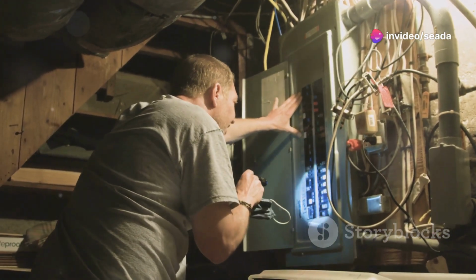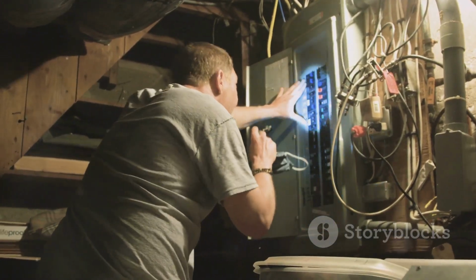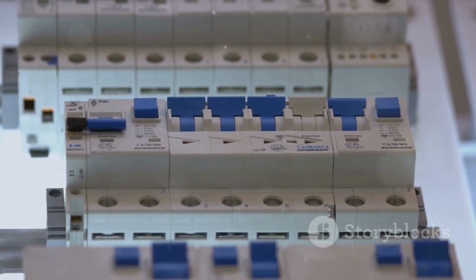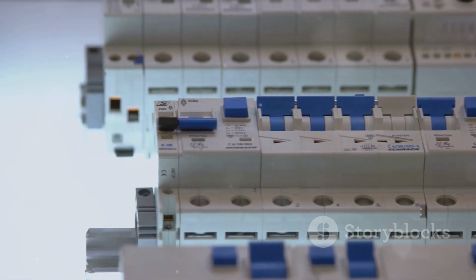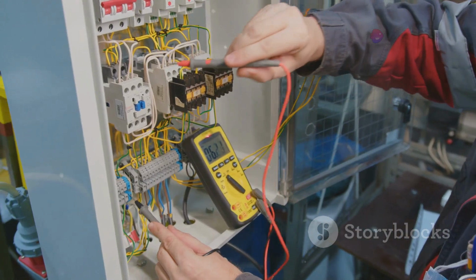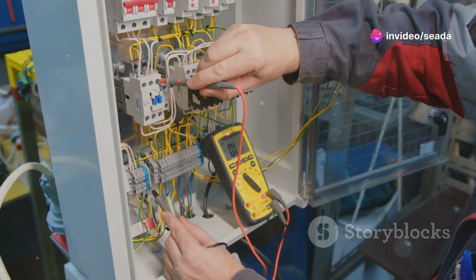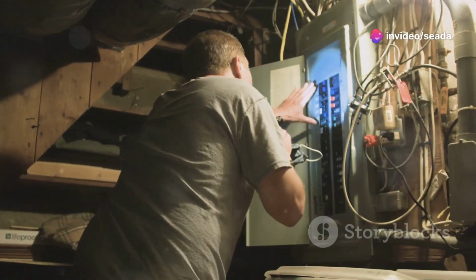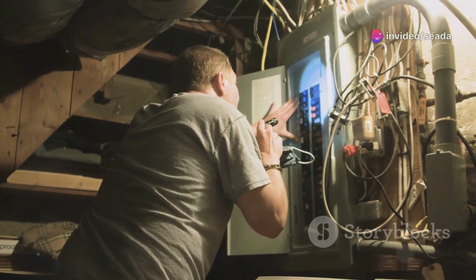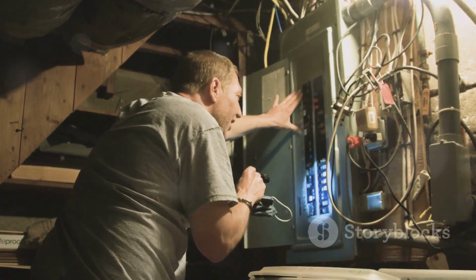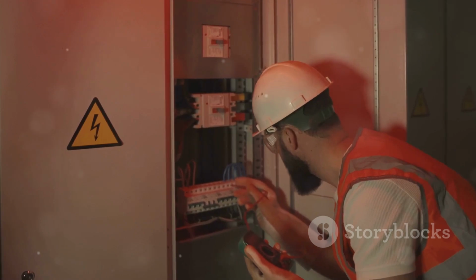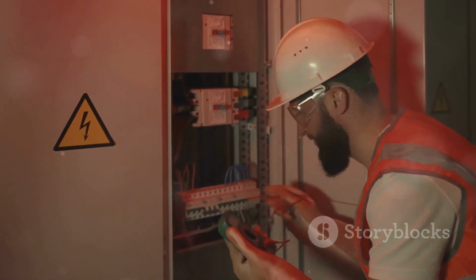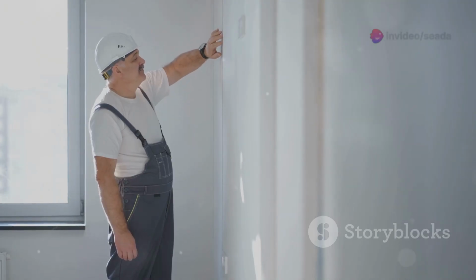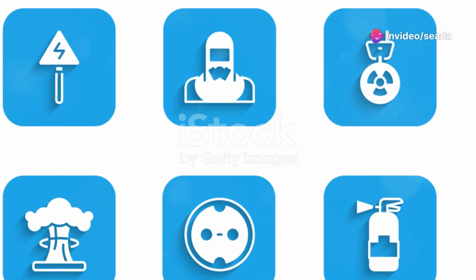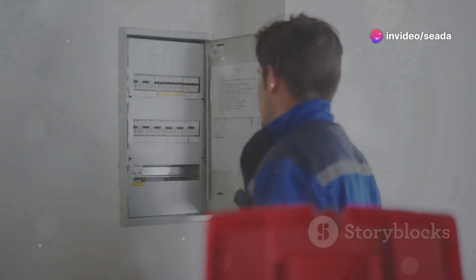If only the upstairs lights are out, focus on that circuit. The consumer unit is your map. Each MCB should be labeled. If labels are missing, identify and label them yourself. Keeping lighting and socket circuits separate means a faulty toaster won't leave you in the dark. This design contains faults and maximizes safety. Understand the layout before you start any work. It's the foundation of safe troubleshooting.